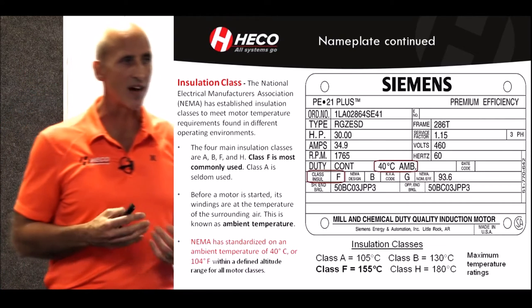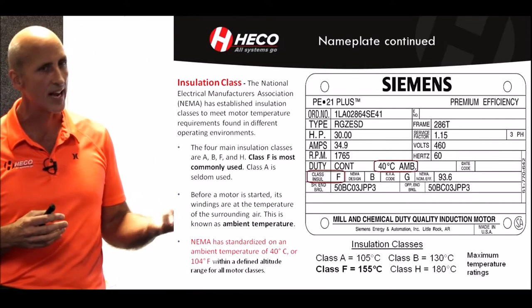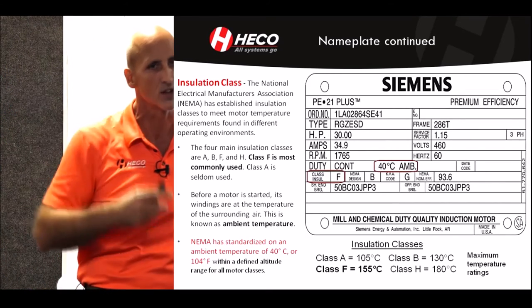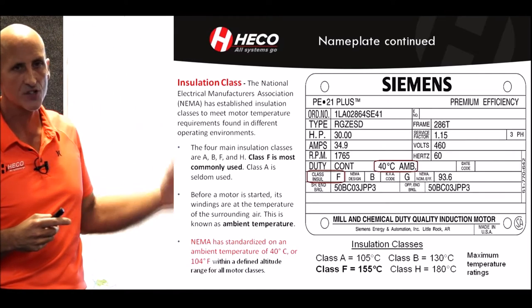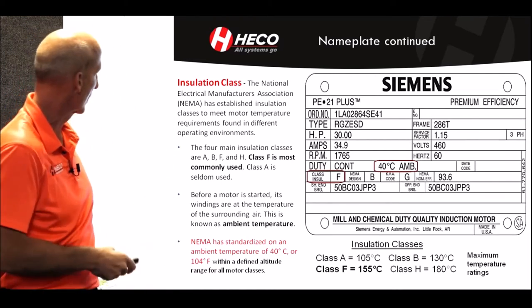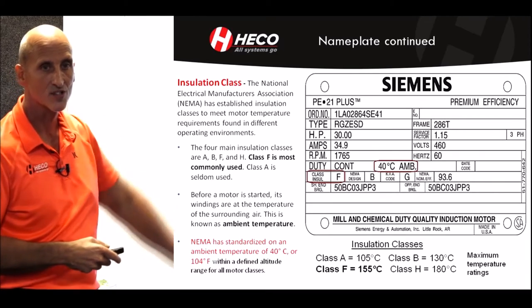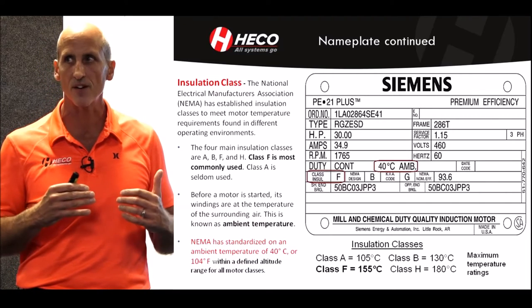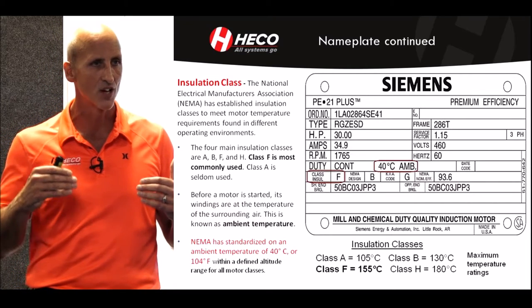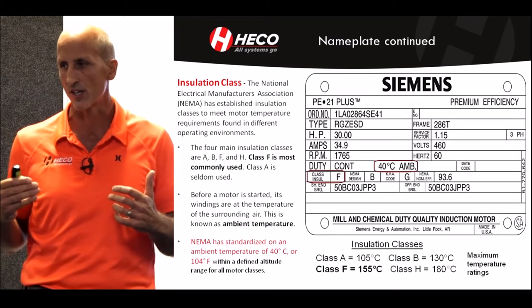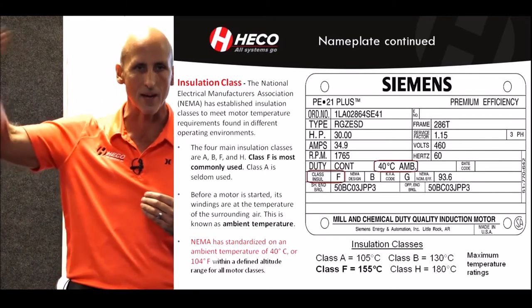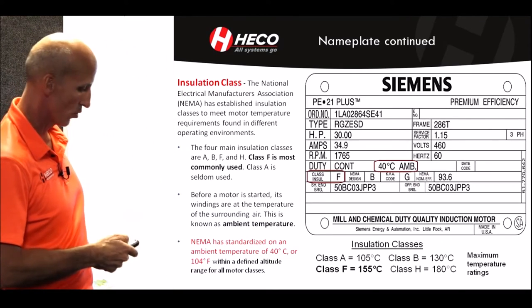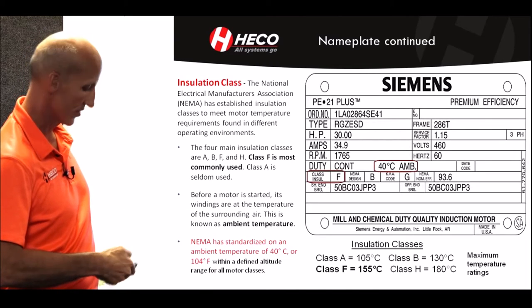Insulation class: NEMA defines the insulation classes A, B, F, and H. Class A isn't used anymore; class B really isn't used much either—you still see those machines out there. It's typically F and H today. NEMA also defines the ambient, and in the United States we define the hottest ambient to be 40 degrees C. The motor temperature rise is added above that. It's a way of defining it and also designing a motor around the insulation system.